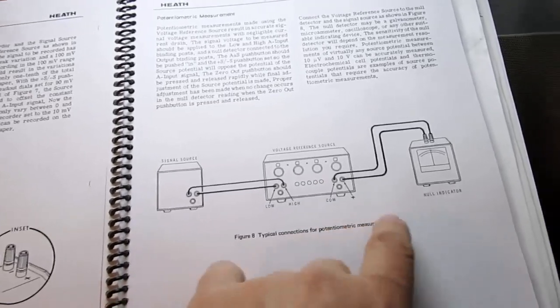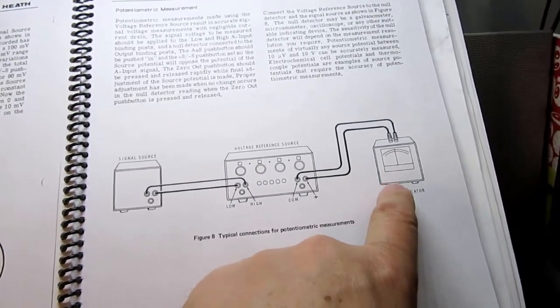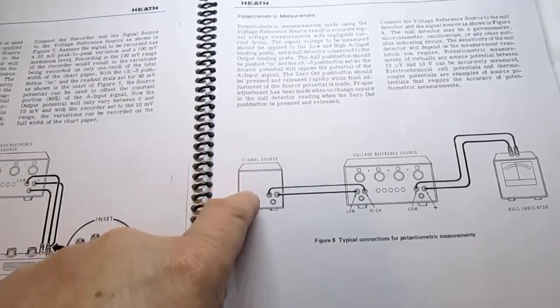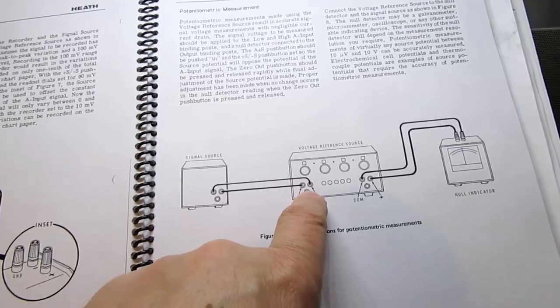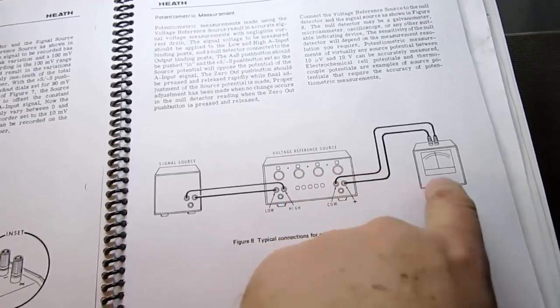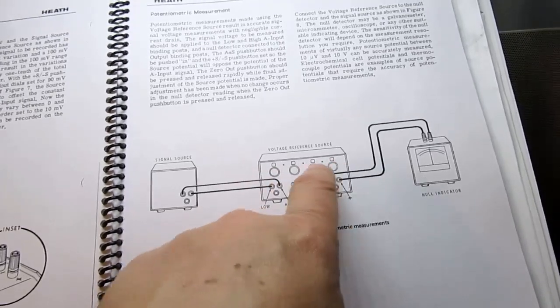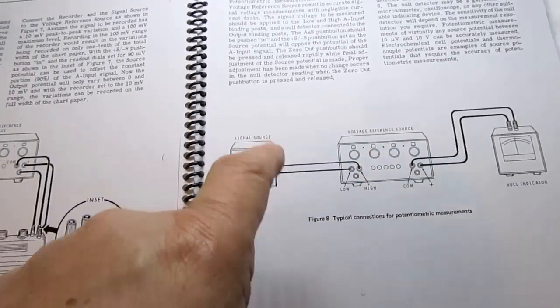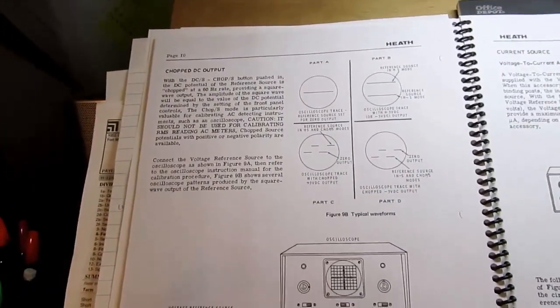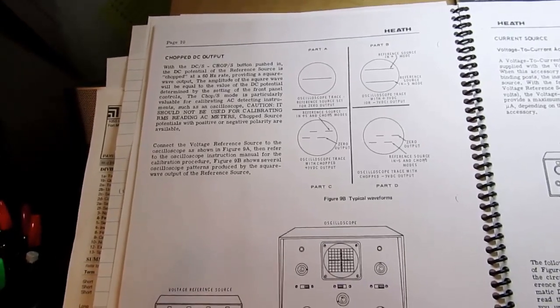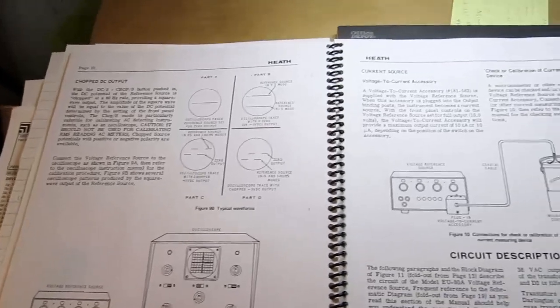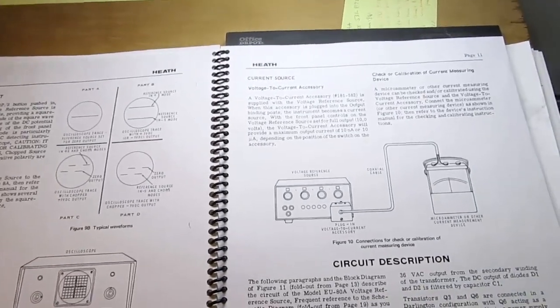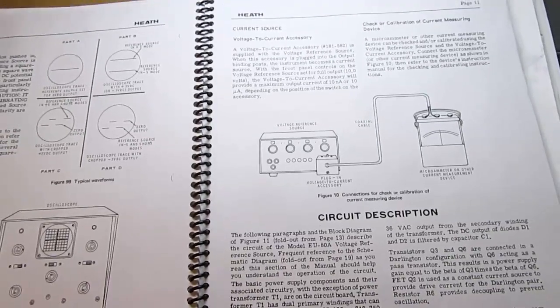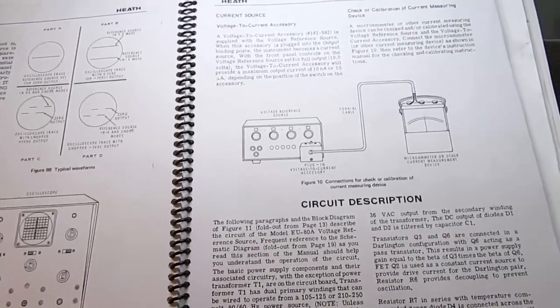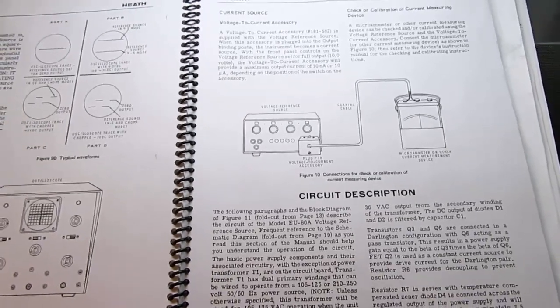So if you only have a null indicating meter and you don't have a precision voltmeter, then you could take whatever signal source you're trying to measure, bring it into this unit, adjust the voltages on here until the meter reads null, and then you can read the voltage off the front panel, and that will be the voltage that you're trying to measure. It also talks about using the chopped DC output, which is useful for calibrating oscilloscopes and other equipment. With the voltage to current accessory, you can calibrate or check current measuring devices, such as microammeters.